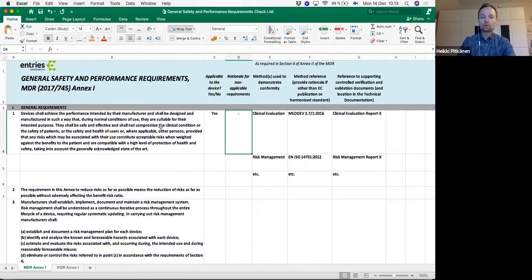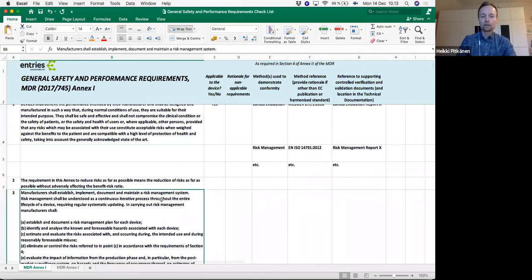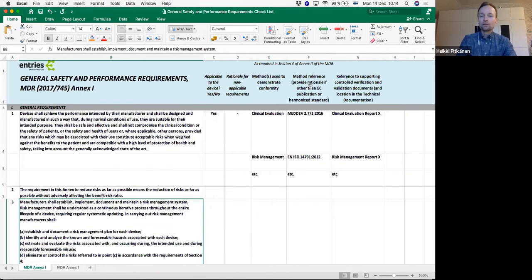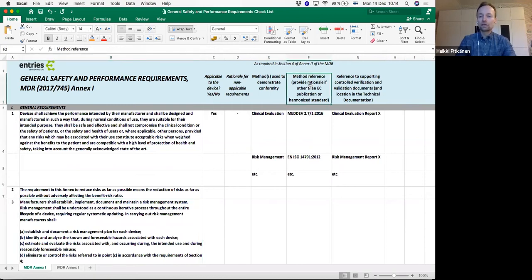And then there may be several means and methods used to demonstrate conformity against one requirement. So it may be that this particular requirement calls for clinical evaluation, it calls for risk management, and it might call for several other methods. And those methods might repeat throughout your table here. So you might use clinical evaluation to tackle this requirement partly, and also the later ones as well. You must provide a reference to the methods, a standard if such is available, like the risk management standard. This is actually the old one. I could change it immediately. And I'm sorry, this is 19, the newest version.